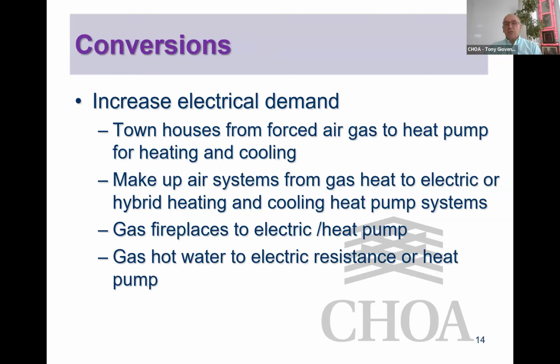We talked about townhouses doing forced air gas to heat pump. It's an interesting thing, but I was trying to recall, the demand from a forced air gas furnace is simply for the circulation pump, the blower. That's all it is. There is no more than that. The demand from a heat pump, however, that is going to be heating as well as cooling in the summer, has a significant increase. And it's interesting because if we look at places like Thompson-Okanagan, where they have hot summers, they plan for this. Heat pumps were a normal part of the life cycle of those zones in those regions.